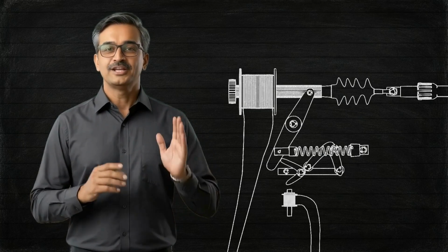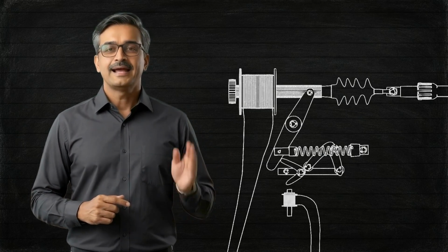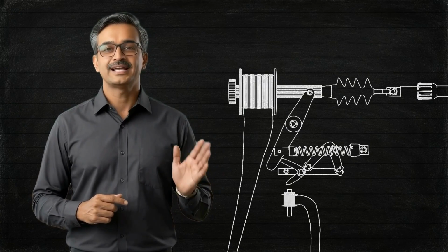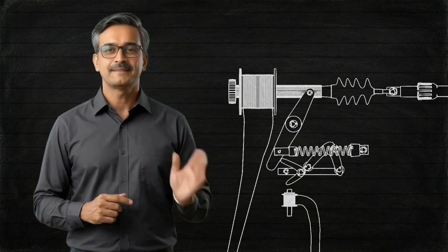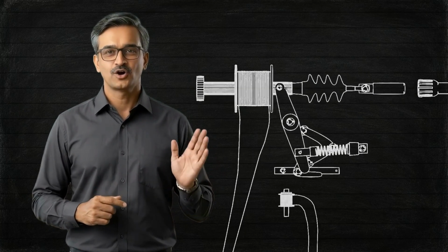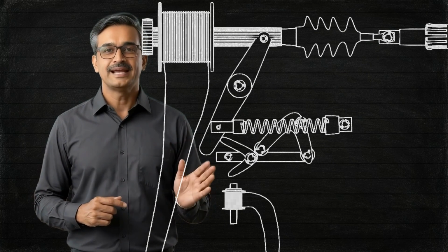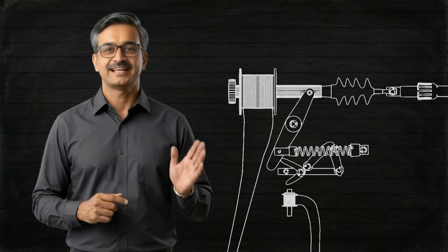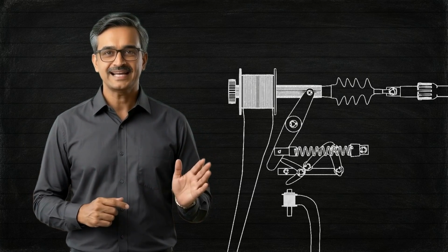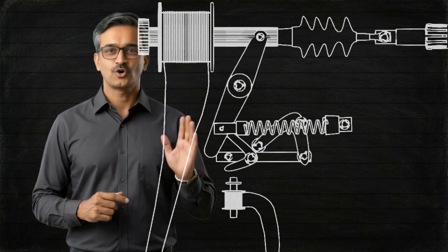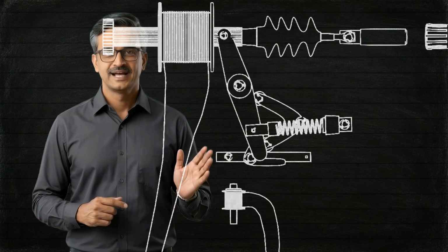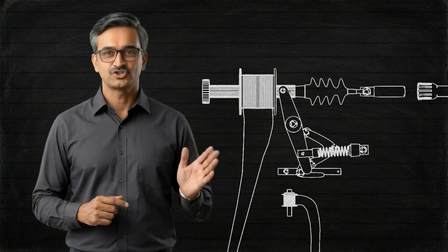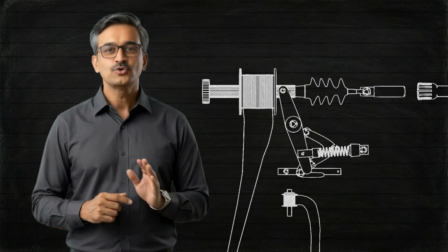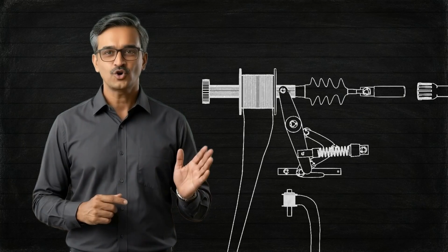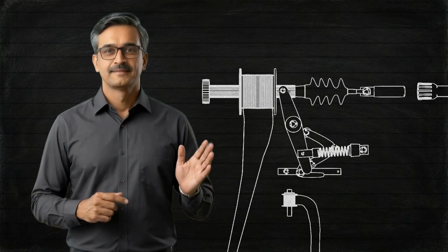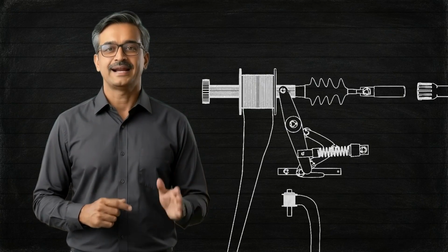But during this closing operation, the movement of the mechanical links, levers, and gears associated with the closing arrangement deforms the spring mechanism. The tripping spring gets charged during the closing operation, and a latch holds the tripping spring in its deformed position. Whenever we send a trip pulse to the circuit breaker, that latch gets displaced due to the action of the tripping coil, which is another smaller solenoid-type device. Once the latch is displaced, the tripping spring relaxes immediately and through the mechanical linkage, pushes the closed moving contact back to its open position. Thus, the opening operation of the circuit breaker is completed.